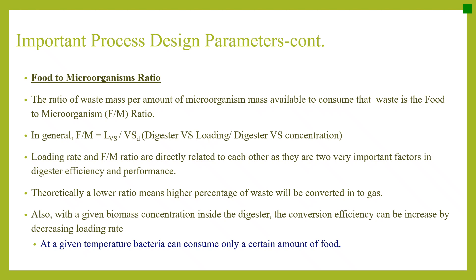The food to microorganism ratio (FM ratio) is the ratio of waste mass per amount of microorganism mass available to consume that waste. FM ratio equals digester VS loading divided by digester VS concentration. Loading rate and FM ratio are directly related and are two very important factors in digester efficiency and performance. Theoretically, a lower ratio means a higher percentage of waste will be converted into gas. With a given biomass concentration inside the digester, conversion efficiency can be increased by decreasing loading rate.